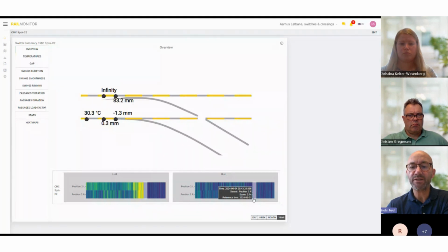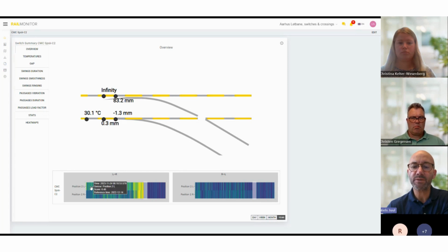The white part here is actually a session where the software creates a learning period. Every single line shows a movement. So this is one event moving from right to left. And this is a 1 year monitoring period that you're seeing here. In the left to right, we see that there are some deviations, and it turns into yellow. The software detects this and creates a warning. So the infrastructure owner then logs into the system and sees, well, what is wrong? Is there something we need to do immediately, or is there something we can do over time?